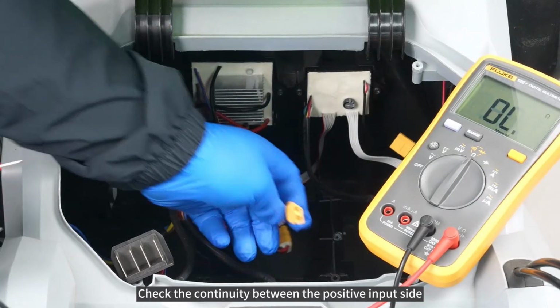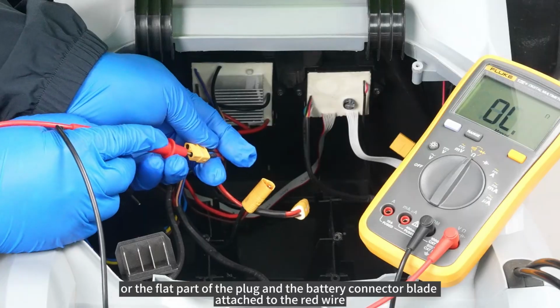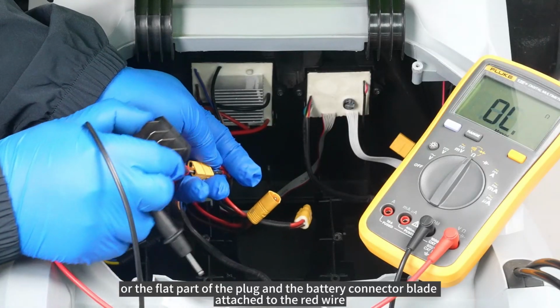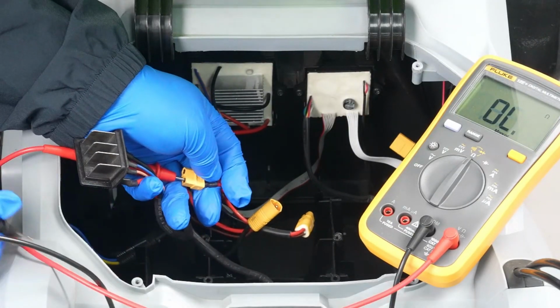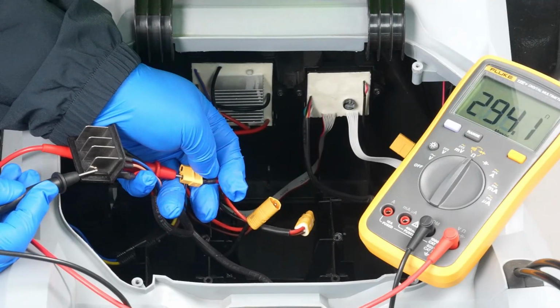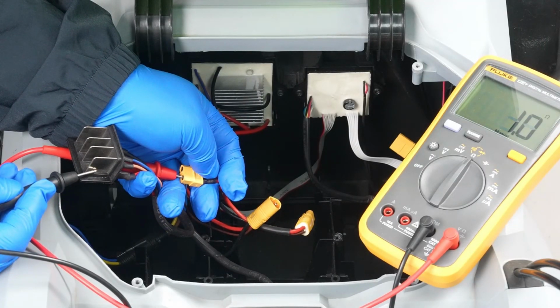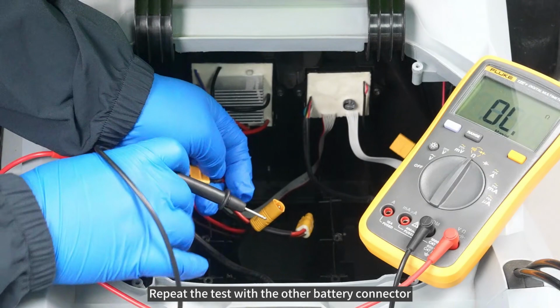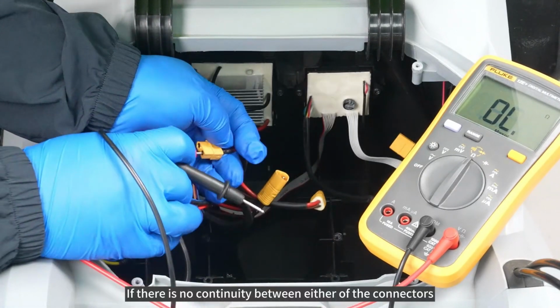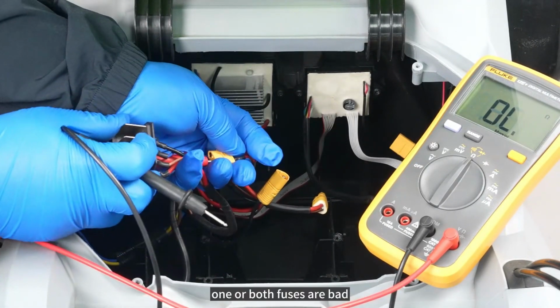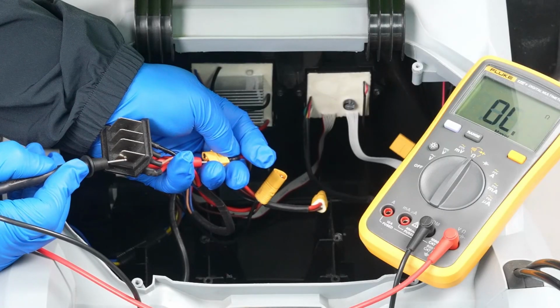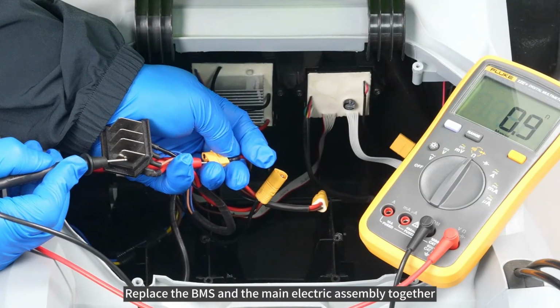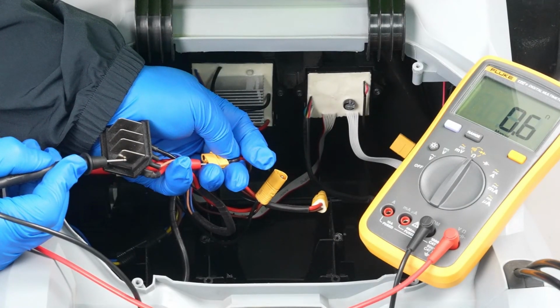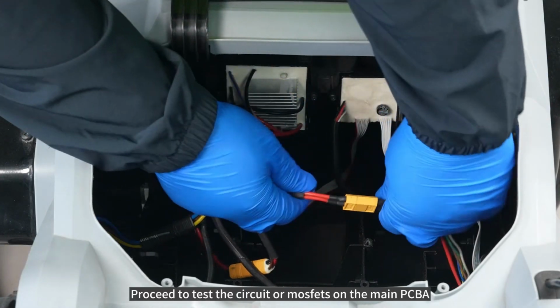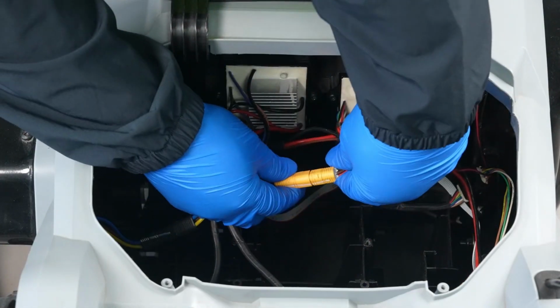Check the continuity between the positive input side, or the flat part of the plug, and the battery connector blade attached to the red wire. Repeat the test with the other battery connector. If there is no continuity between either of the connectors, one or both fuses are bad. Replace the BMS and the main electric assembly together. Proceed to test the circuit or MOSFETs on the main PCBA.